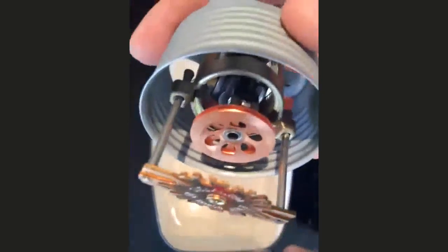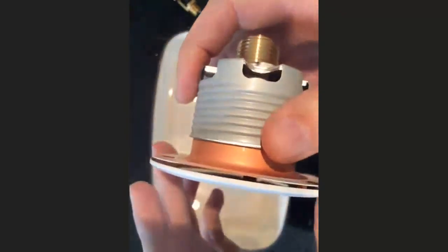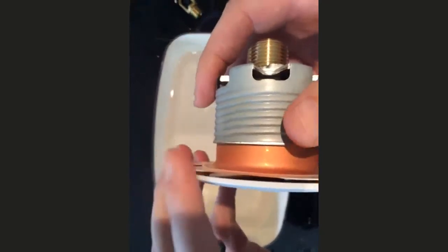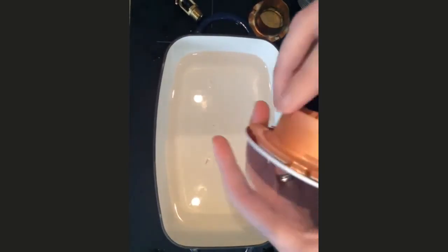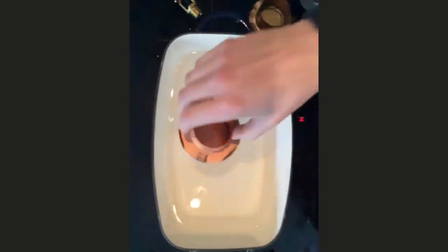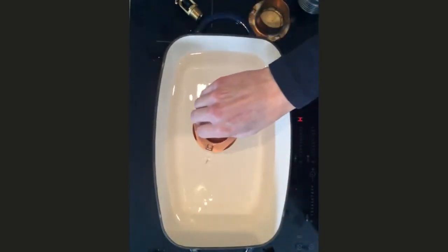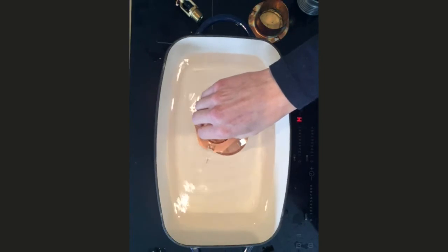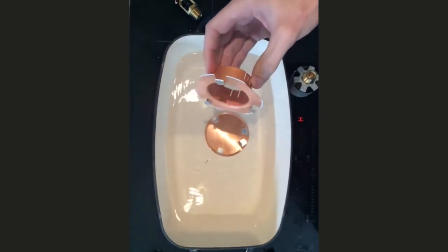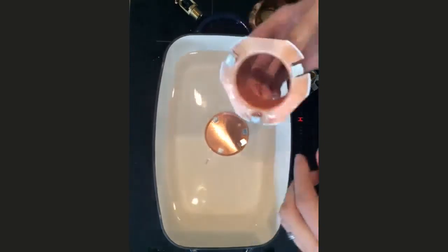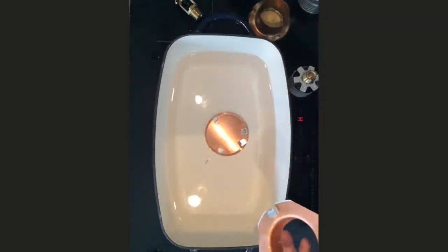So yeah, just going back to this concealed sprinkler head. So that's it there with the cover plate on, and I'll just show you the cover plate coming away. So I'll just show you how that works. So here's our cover plate. If I just dunk that in the water, whoosh, and that's come apart. So quite readily. This one's in 3 pieces.